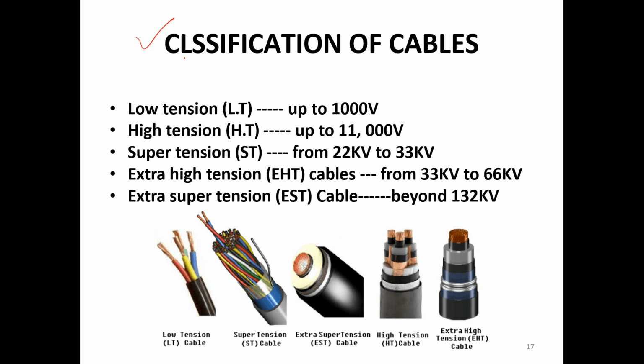How do we classify cables? They are broadly classified into 5 categories. Low tension and low voltage mean the same thing, so don't confuse these two terms. Low tension cable is up to 1000 volts. High tension or high voltage cable goes up to 11 kV. Super tension or super voltage is between 22 kV and 33 kV. Extra high tension, which we call EHT, covers cables from 33 kV to 66 kV. And extra super tension or extra super voltage cable is beyond 132 kV.